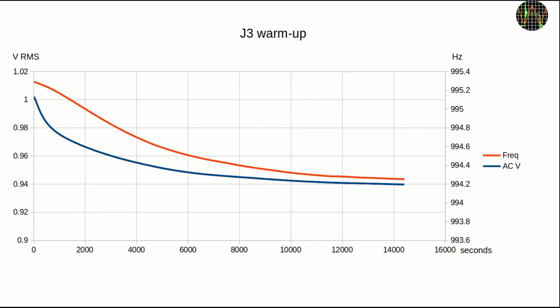Before expecting any frequency or amplitude consistency from the J3, you better let it warm up a while, and depending on how important a constant frequency or amplitude is, that while may stretch to 3 or 4 hours. I'm beginning to understand why this unit was probably never turned off. To be fair, the frequency is actually fairly constant, just a bit more than 1 Hz over all that time, or 0.1%. Over the same time, the amplitude dropped by about 6%.